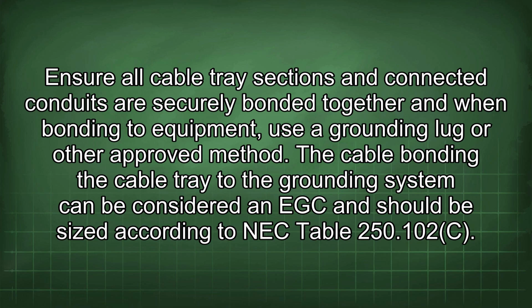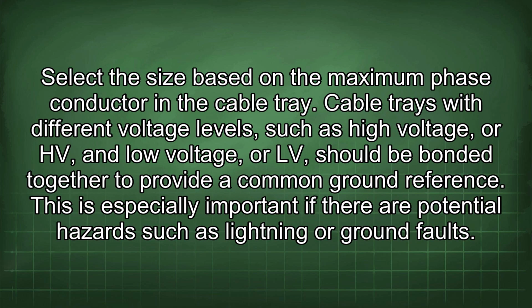The cable bonding the cable tray to the grounding system can be considered an EGC and should be sized according to NEC Table 250.102(C). Select the size based on the maximum phase conductor in the cable tray.